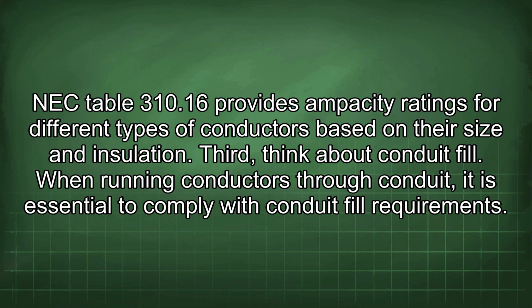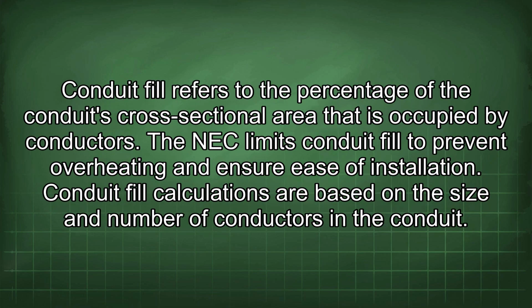Third, think about conduit fill. When running conductors through conduit, it is essential to comply with conduit fill requirements. Conduit fill refers to the percentage of the conduit's cross-sectional area that is occupied by conductors. The NEC limits conduit fill to prevent overheating and ensure ease of installation. Conduit fill calculations are based on the size and number of conductors in the conduit.